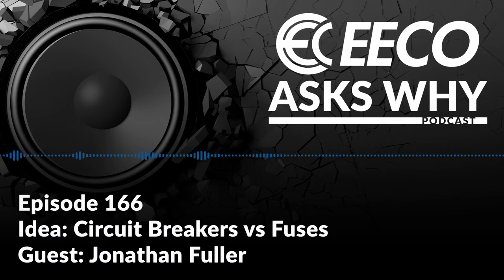Right, right. So maybe let's talk through advantages of each, because each one does have advantages, right? Right. So again, fuses are less expensive. They're going to quickly react to that overload. So it's typically for more sensitive electronics that you're going to want to have that fuse on it. But one of the disadvantages of a fuse is that if you've got a circuit that's usually going to have some inrush current or overcurrent or surges on it, that's going to cause those fuses to blow a lot. Another disadvantage of a fuse is typically, unless you've got a great vendor managed inventory through us here at EECO, you're not necessarily always going to have that extra fuse laying around. So sometimes customers will go in and select the wrong fuse to replace that with.